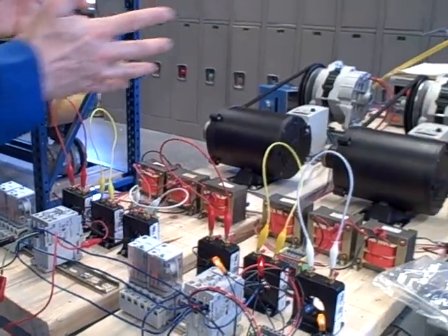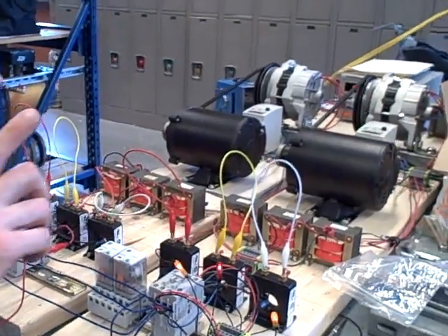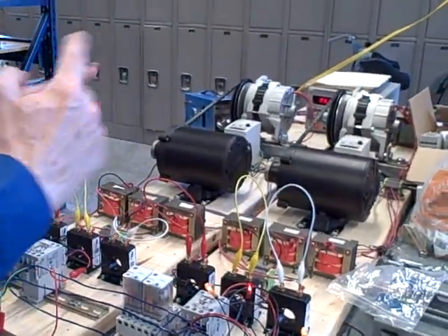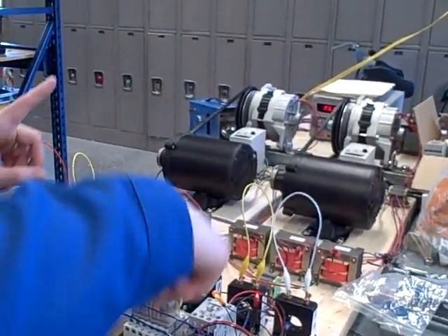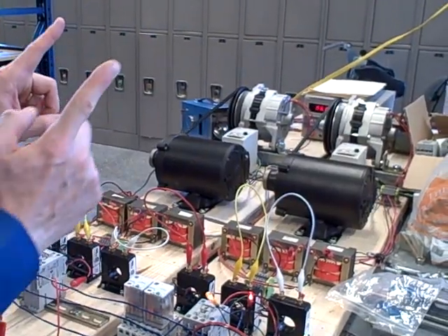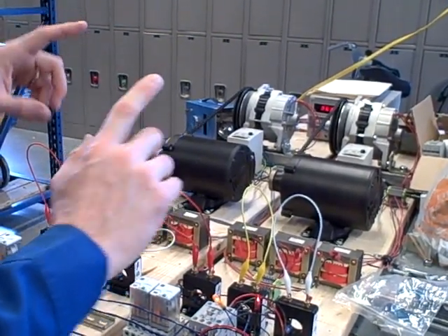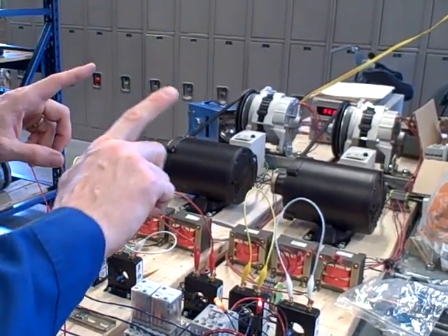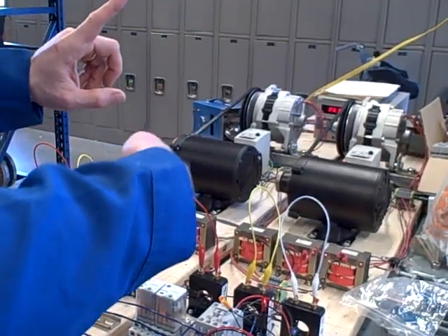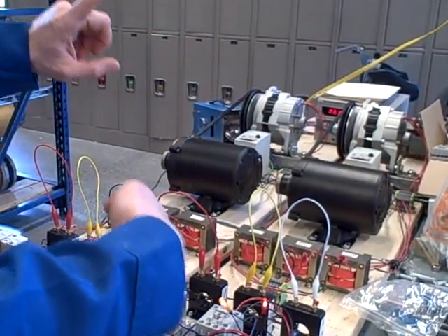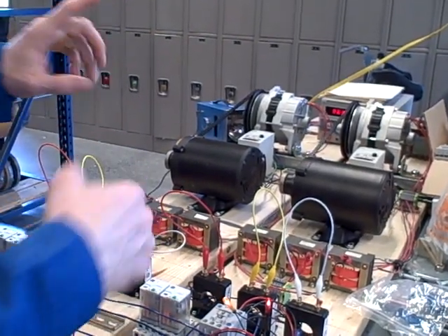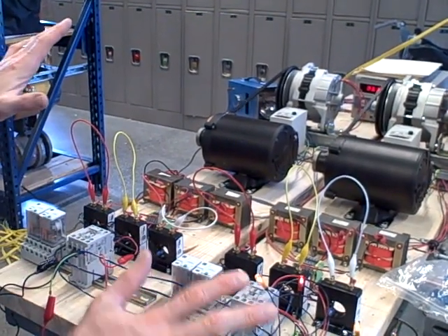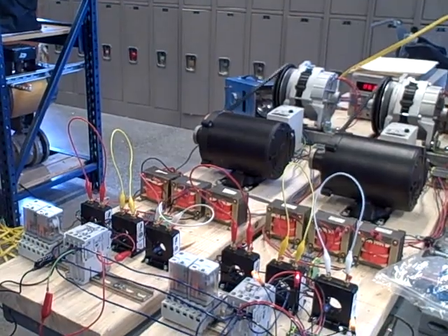Well, AC generators are kind of like batteries that are spinning around. So as they spin around and come in phase with each other, they have the same polarity. But if you let one of them spin at a different speed until it's opposite, they've got opposite polarities. If you try to close that breaker then, bad news, short circuit.